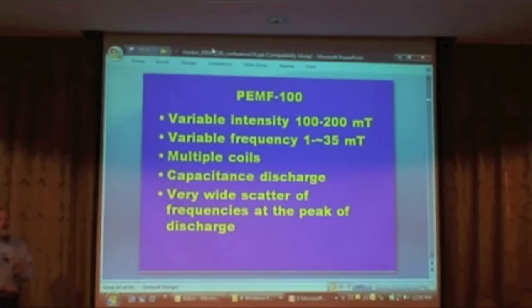100 millitesla is 1,000 Gauss. A Tesla is 10,000 Gauss. Most MRI scanners are somewhere between 2 and 12 Tesla. Okay, so you're talking about tens of thousands of Gauss, between 20,000 to 100,000 Gauss. All right, so what we have then is a fairly low-level system. It's about 0.1 to 0.2 Tesla. Okay, it's a tenth to a fifth of a Tesla.